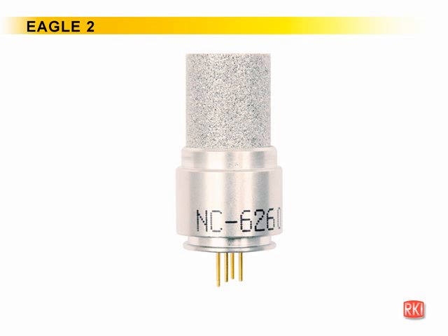The Eagle 2 provides the catalytic combustible sensor with some protection against exposure to high levels of combustible gas, which can damage the sensor. It does this by turning off the combustible sensor power temporarily when it determines that an overscale concentration of combustible gas is present that may damage the sensor. Nevertheless, concentrations of combustible gas of more than 100% LEL can still affect the zero level or calibration of the combustible sensor if the concentration is high enough.